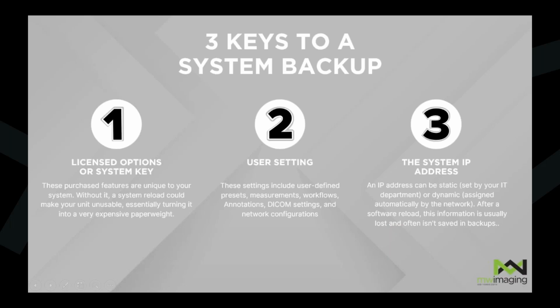You want to make sure that the user settings are backed up. These settings include user-defined presets, measurements, workflows, annotations, DICOM settings, network configurations. And finally, I want to make sure that I have the system IP address backed up as well, so that I know what that is, so I can get it back on the network quickly. There's usually 2 types of ways that it's assigned to the system. It's either static, which is assigned by the network administrator, or dynamic, which is automatically assigned by the individual PC or the network itself.